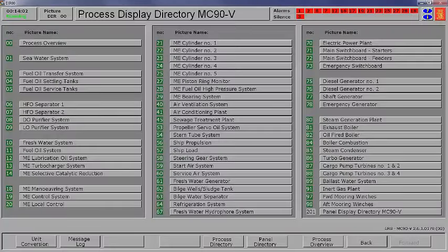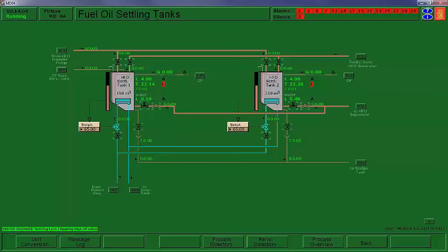We went from transfer system, let's go to settling. The set points are already given to you, but one of the things I want you to note is 65C. The minimum flash point of marine fuels is 60. So technically, even at this low set point of 65C, the vents coming off of this, if you put a lighter beside it, you could get a flame. So something to think about. We're going to heat both of these tanks to 65, and that's a pretty normal temperature.